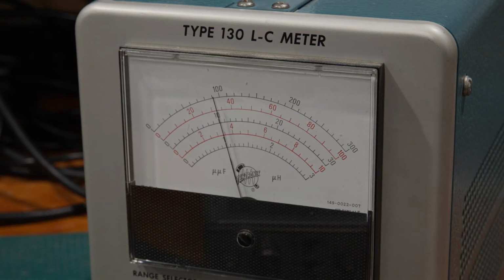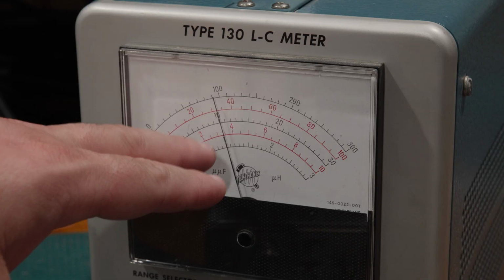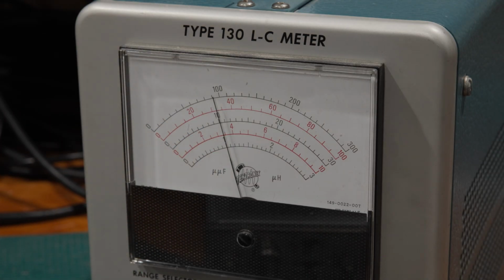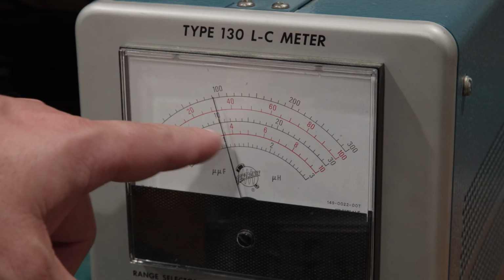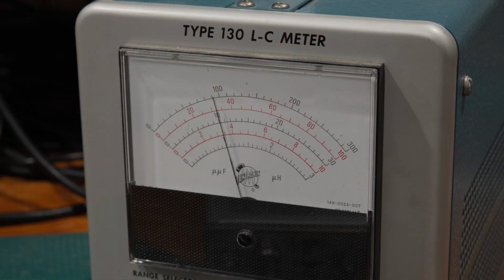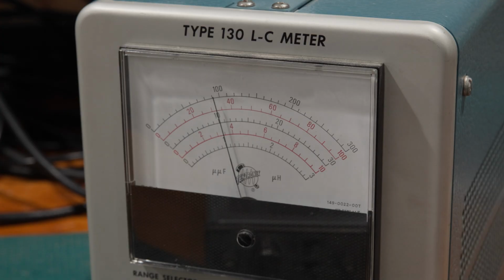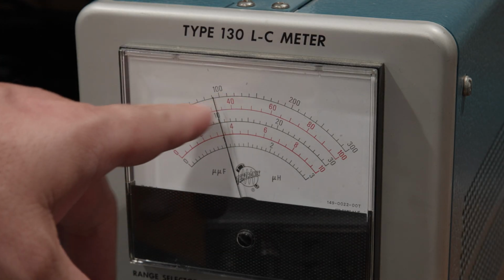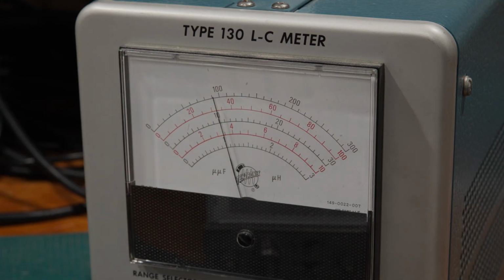Now, that's actually pretty accurate. We got the 15, and this particular plug-in is rated at 20 picofarads. So this is actually not too bad. We're down at the bottom of the range, so our accuracy is not the best, but we're within the ballpark. But I wouldn't want to adjust here. What I'd be adjusting would be a little too much, and I really wouldn't be able to see what's going on. So we've got to think about something a little different.